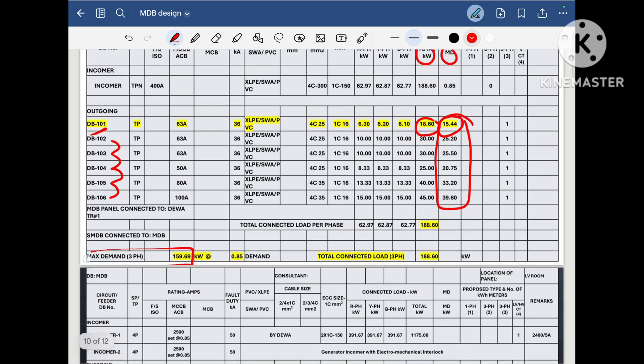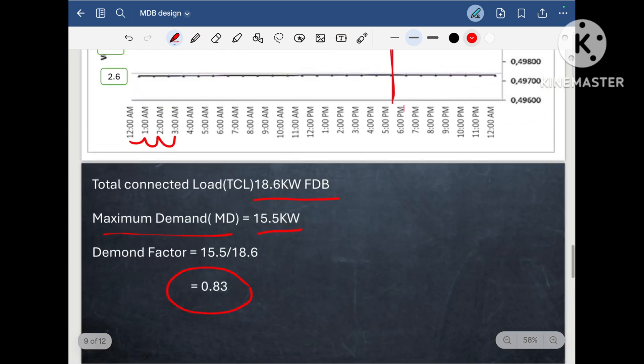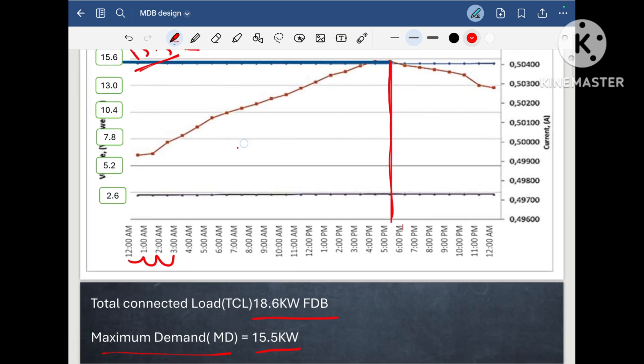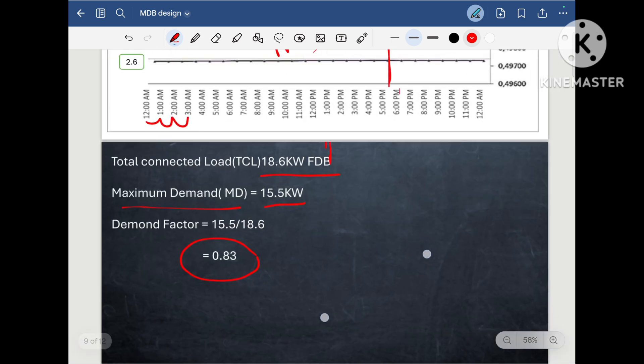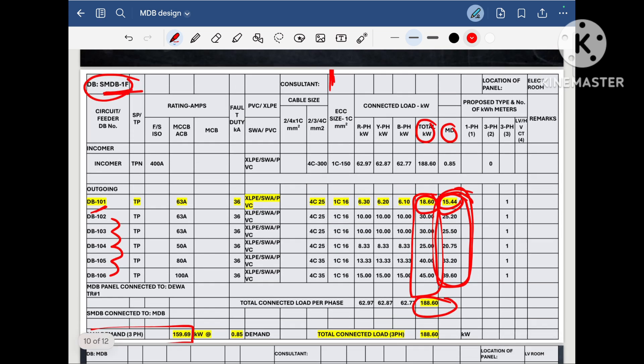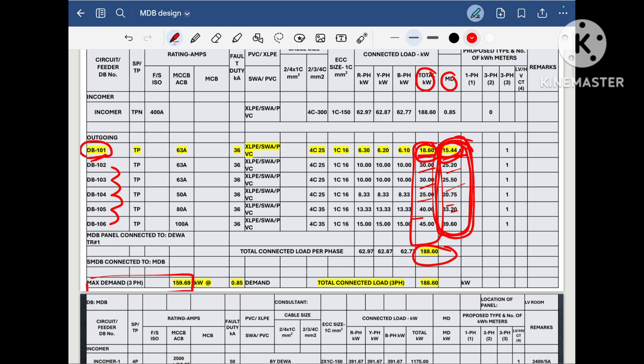Here you can see the maximum demand on this SMDB is 159.69 KW when we sum all the DB maximum demands. And what is the total connected load? The total connected load is the sum of all DB connected loads, which is 188.6 KW. For DB1, the total connected load is 18.6 KW and the maximum demand is 15.45. I followed the same procedure for other DBs and tabulated total connected load and maximum demand. Summing up the total connected load gives the total connected load on SMDB1F, and summing the maximum demands gives the maximum demand load on SMDB1F.